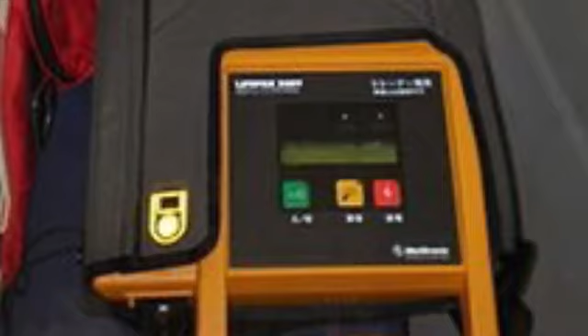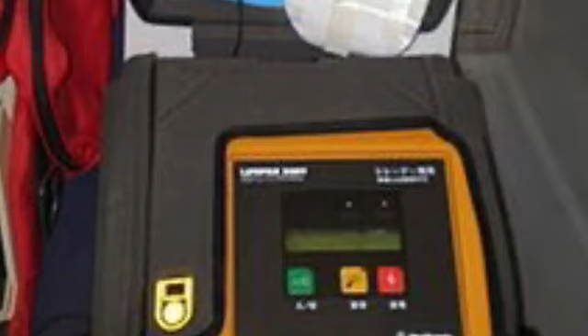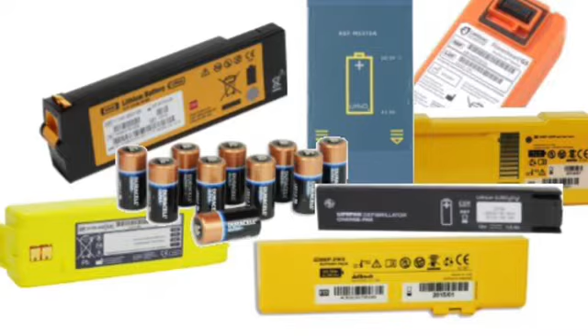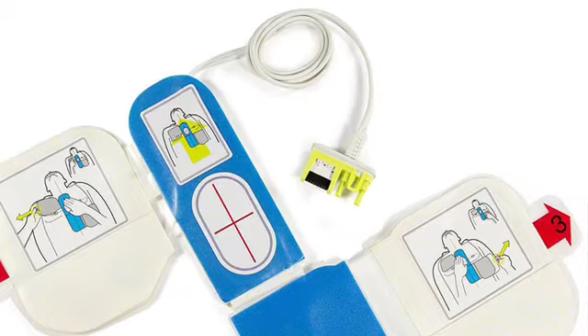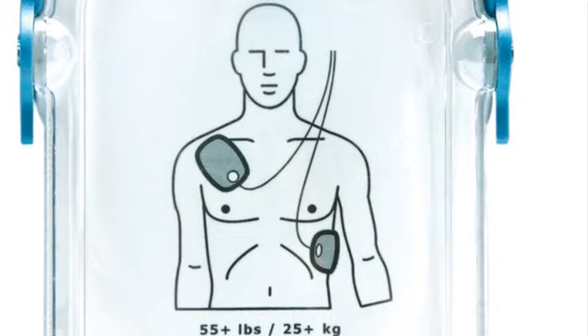They're not as small as our iPhone, but they're getting there. So with the AEDs, they actually have a battery that we have to check to make sure it's fully charged. It also has pads that expire every 2 years, so if we have an AED where we work, or at a school, somebody should be checking it frequently to make sure it doesn't need service, whether it's replacing the batteries or replacing the pads.